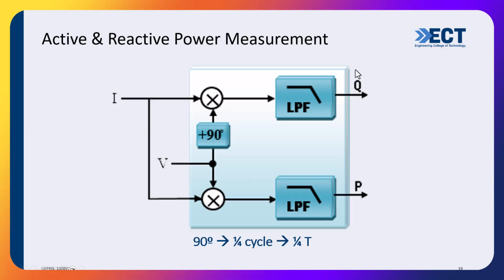But to generate reactive power - and I think reactive power is known to all of you, it's the imaginary power consumed by machines and any inductive or capacitive load - that can be calculated by shifting the voltage signal by 90 degrees and then multiplying it by current, and through a low pass filter we can get the reactive power.